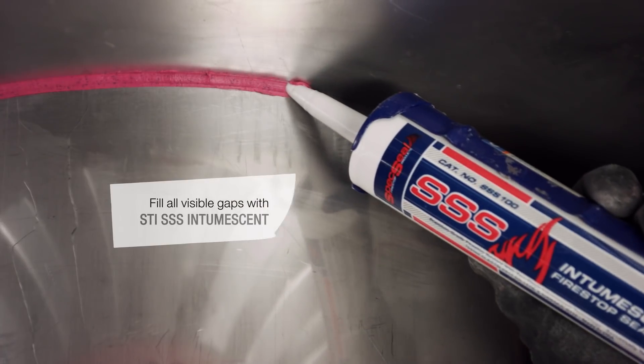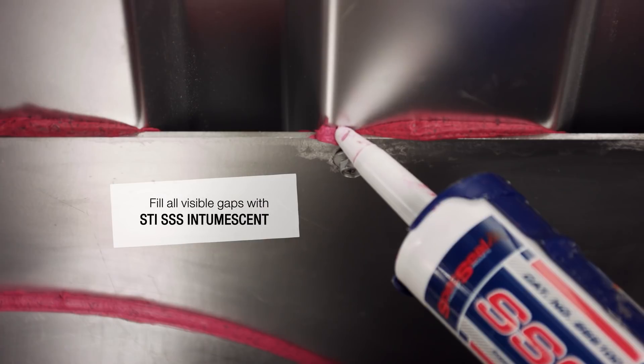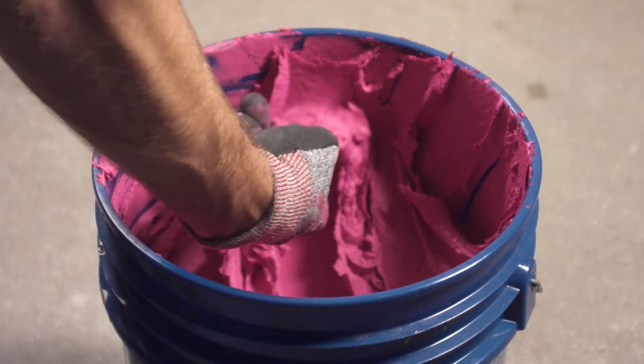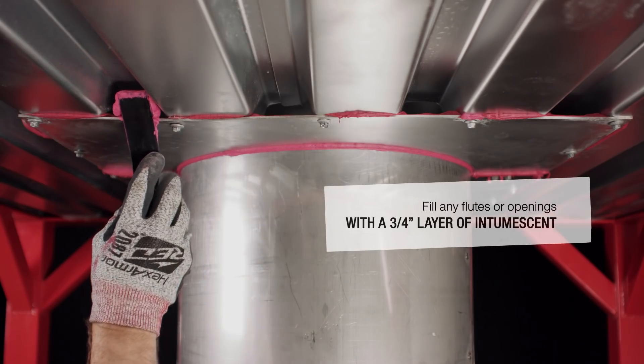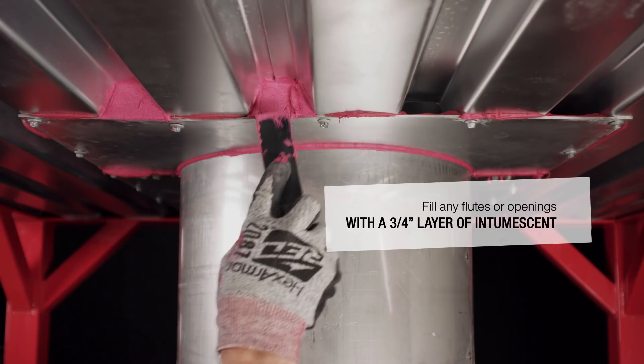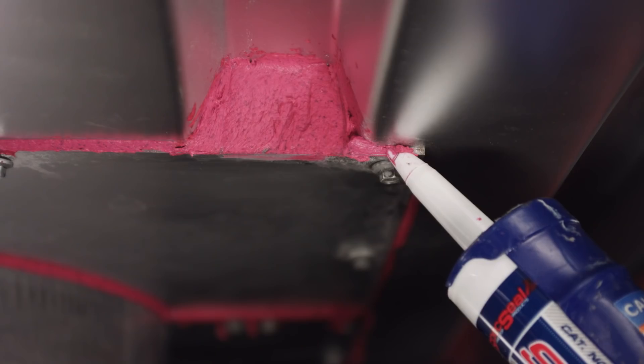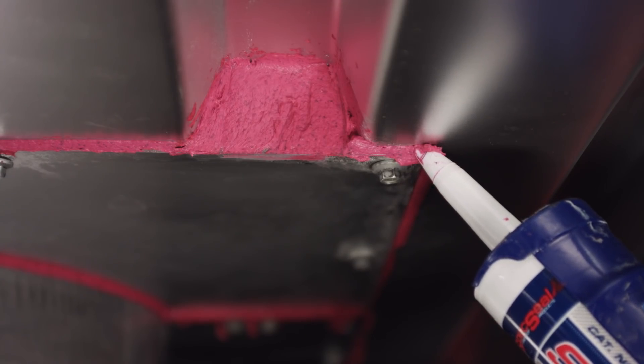Fill all gaps around the duct and the edges of the fire plates using intumescent. If your floor type contains flutes or openings as shown here, fill them with a three quarter inch layer of intumescent. Otherwise, just ensure the fire plate is sealed all the way around.